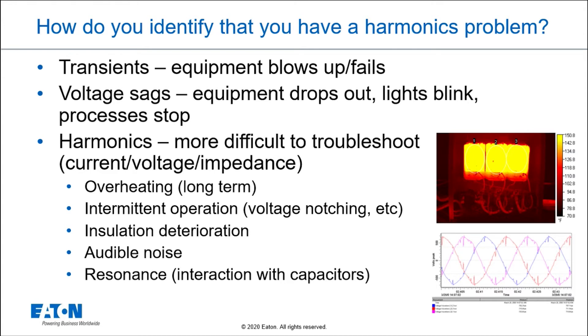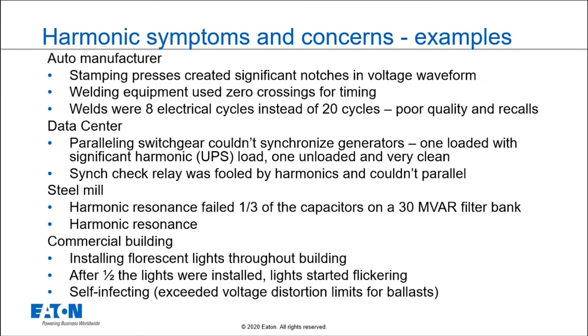Audible noise is an interesting one. Electrical equipment really isn't supposed to make noise, but if you've ever energized a transformer and heard that tuning fork sound, that's basically harmonics — second, third, fourth harmonics. It's a short-term thing, but it is actually harmonics. The kinds of noises you hear on equipment may or may not give you an indication of harmonic issues. With resonance, it's super important to understand how resonance plays into harmonics, especially as we add power factor correction capacitors.